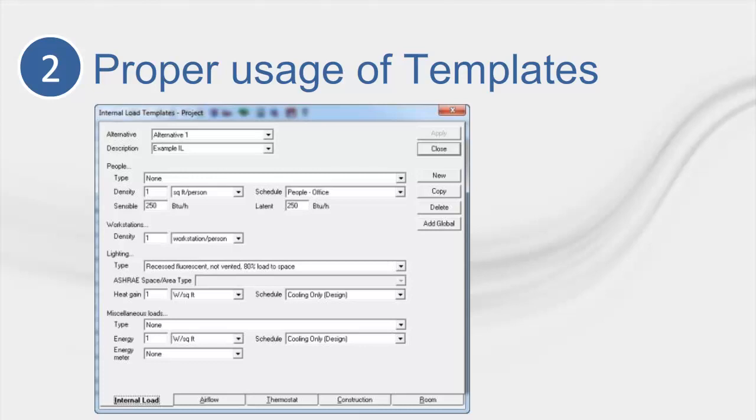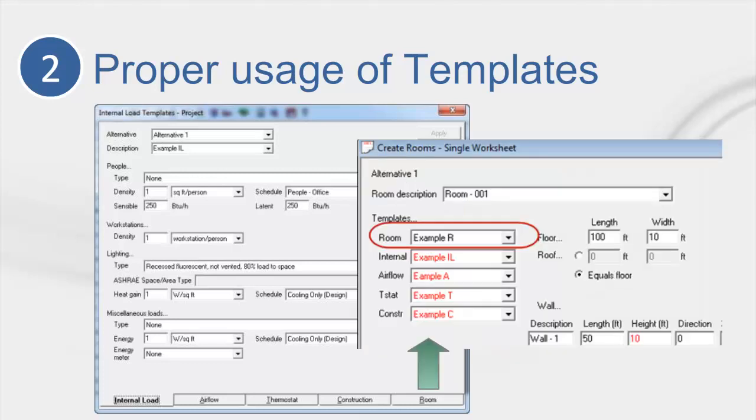As a general rule of thumb, you want to make enough templates to describe the different zones and rooms in your building. For instance, the Internal Loads tab normally contains the most templates. This is because this is where the most diversity resides. However, the Construction tab may only have one or two templates, because typical buildings use the same construction materials throughout. Finally, you need to take advantage of the Rooms tab. This is where you combine the Internal Loads, Airflows, Thermostat, and Construction templates into one master template for each room type. Once these master templates have been created, you can fill in the majority of a room's inputs with a single click.